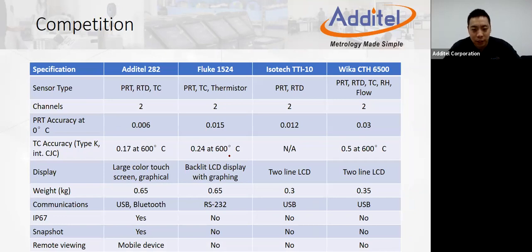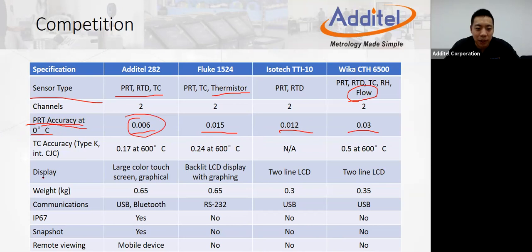About the specification: sensor type, the 282 can measure PRT, RTD, and TC. Some other items can also test NTC or flow, something like that. For accuracy, PRT measurement accuracy at 0 degrees C, we have 6 milliK. This is just a readout accuracy, it doesn't include the probe. But for the others, we have 15 milliK, 12 milliK, or 30 milliK. So we have a much better accuracy right here.